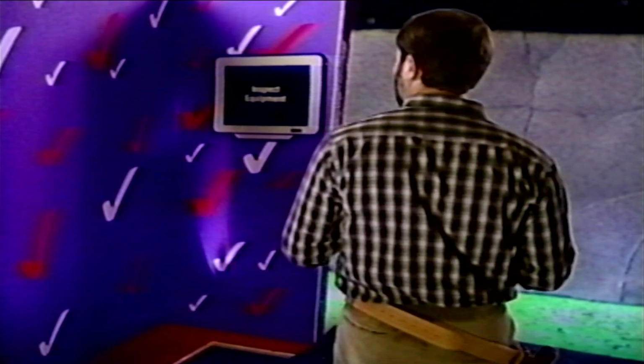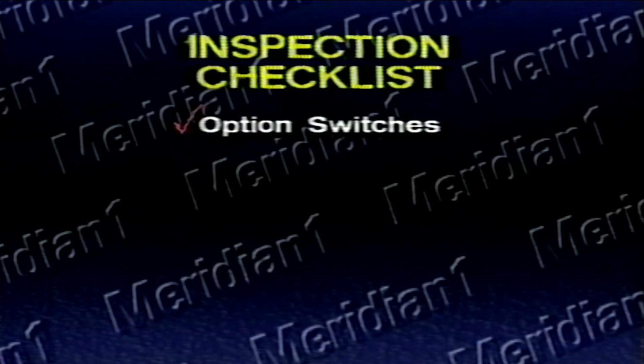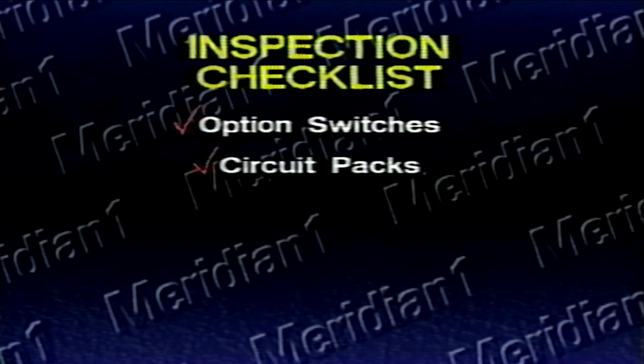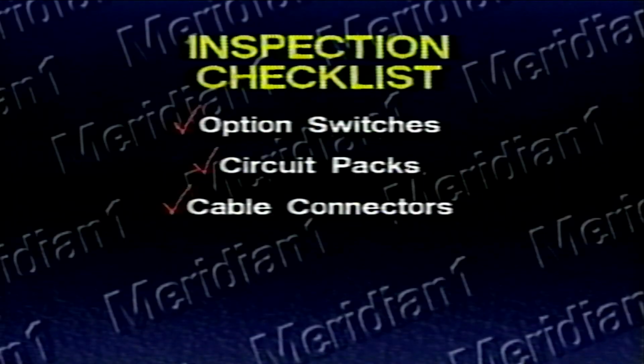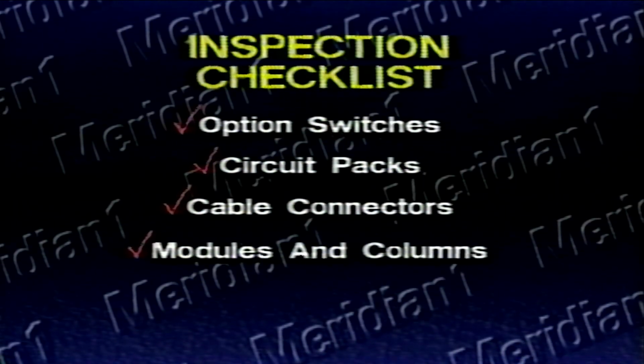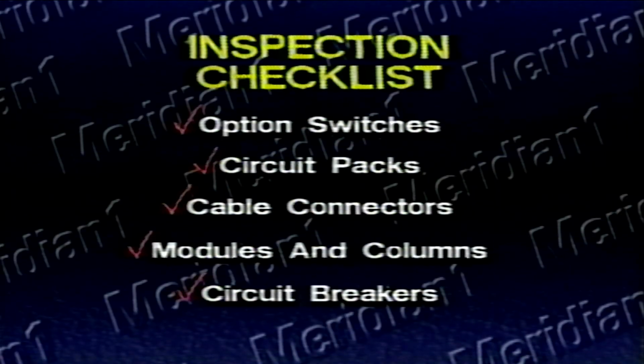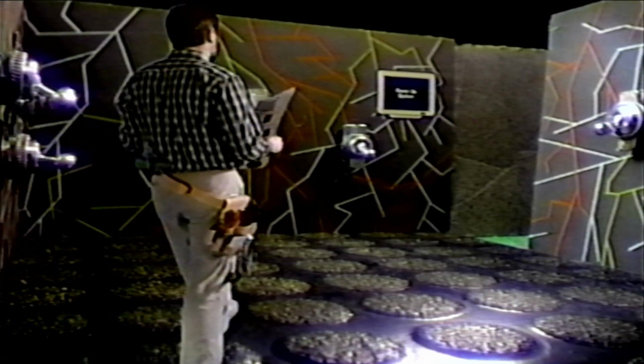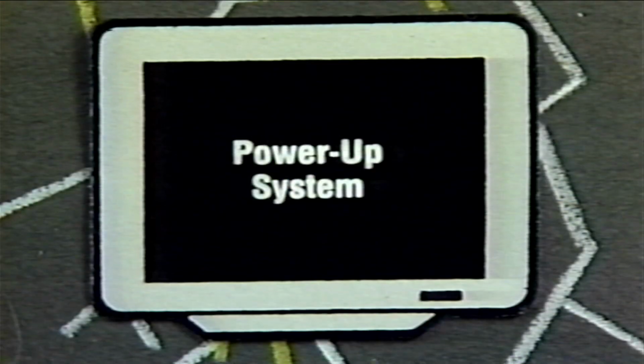At this point in the Meridian1 installation, it is vital to perform an inspection of all the equipment. Check to see that you have properly set all option switches, plugs, and faceplate switches, seated and locked all circuit packs in their assigned positions, secured all cable connectors, properly designated all modules and equipment columns, and set all circuit breakers to the off position. You can add items to this checklist to ensure that all equipment installation tasks have been performed before you power up the columns. To ensure proper operation, follow the system power-up instructions very carefully.